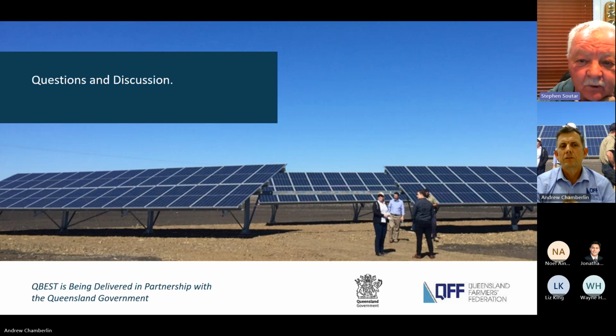Yeah, and at Willandra during that project, we did automatically control a remote NMI based on solar at a different NMI. And we proved that we were able to absorb and pretty much put a bubble around the plant and end up with zero export. Now, I think that's really important going into the future. But again, I think the biggest problem that we need to resolve moving forward is what we're doing with tariffs, because it's tariffs that stop you doing that.